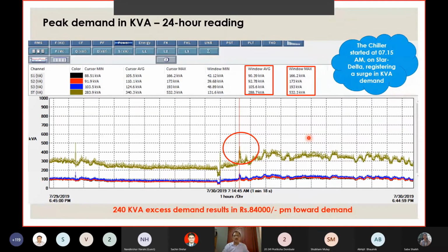So this is another thing that comes out of the same full day recording. As you can see here, 240 kVA excess demand has resulted in this facility paying approximately 84,000 rupees more every month towards the additional demand. So this can help them to recover. This will be approximately 10 lakhs in a year. A VFD for this demand would probably cost less than 10 lakhs. So in less than a year, they will be able to recover the investment and ensure that the demand that is more than required is surrendered.